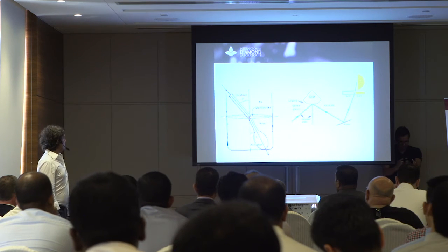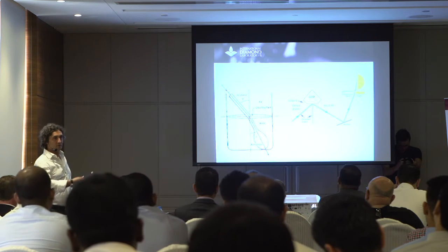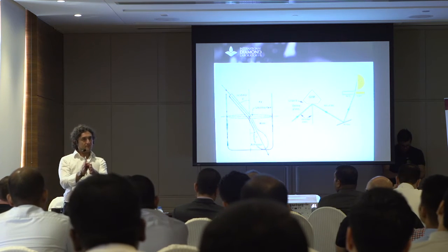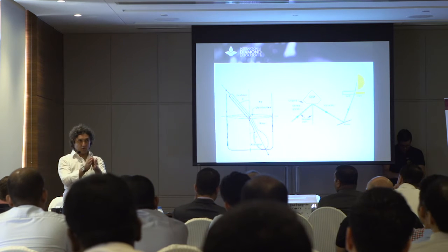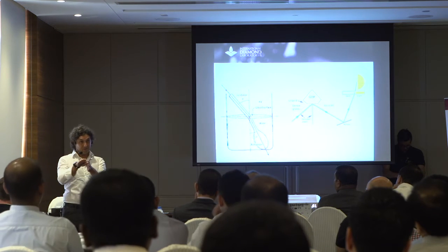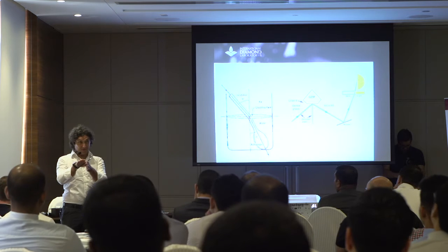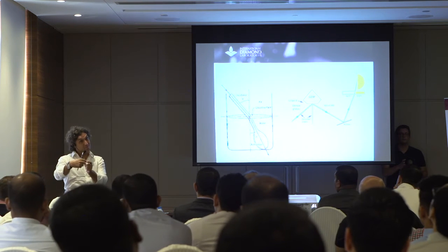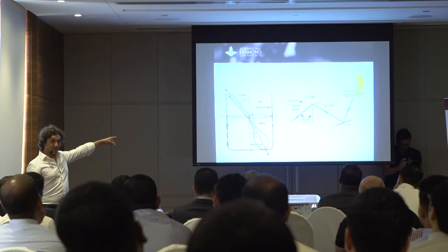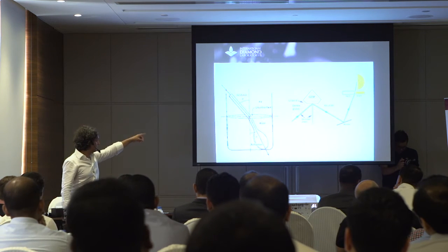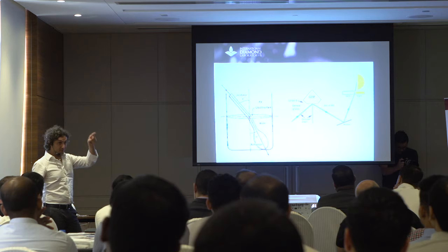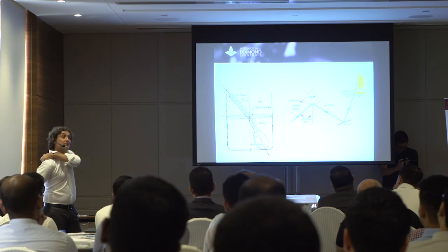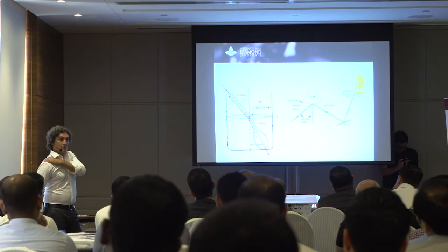Of course, there is a formula, but we don't have to apply the formula. We have that scale. The refractometer itself is built according to a certain alignment. If you mess with the scale, you get another number. So it's been placed at the right place because the optical path of the reflection has to be correct. Then you get the right refractive index.